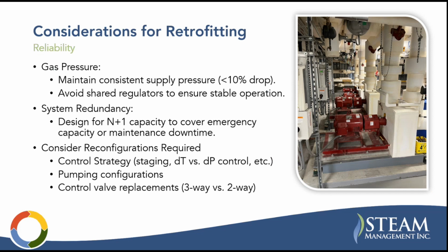Gas pressure is, these boilers are a little bit more finicky with gas pressure. You want to maintain a consistent supply. You want to have dedicated regulators for each boiler, where, on conventional boilers, it might get away with one common regulator. These you're going to want to have one on each boiler's fuel train. And you want to keep it within a 10% drop.